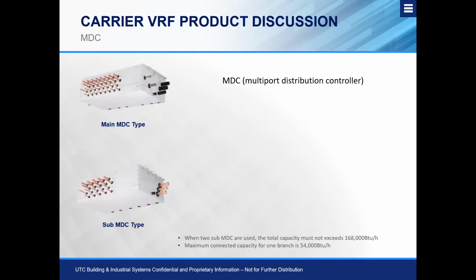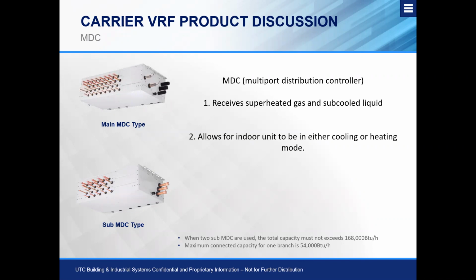All right, so we talked about the heat pump and heat recovery side of things. So let's look at our MDCs, flow selectors, branch boxes, or essentially the heart behind the heat recovery system. So we need to understand, one, terminology, which is the branch box. But two, we need to understand really what is the purpose of this MDC. First, it's going to receive superheated gas and subcooled liquid coming from our outdoor unit. It's going to allow for the indoor unit to be in either a cooling or heating mode for that simultaneous operation, or what we refer to as heat recovery.